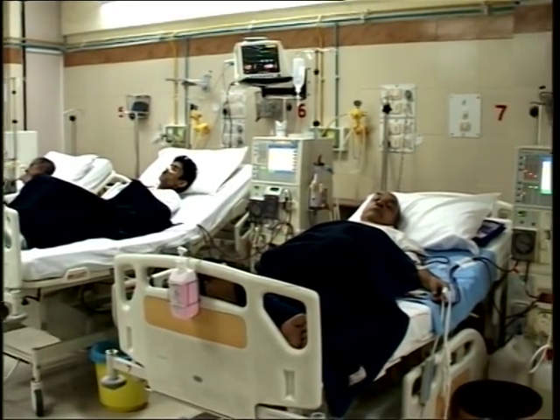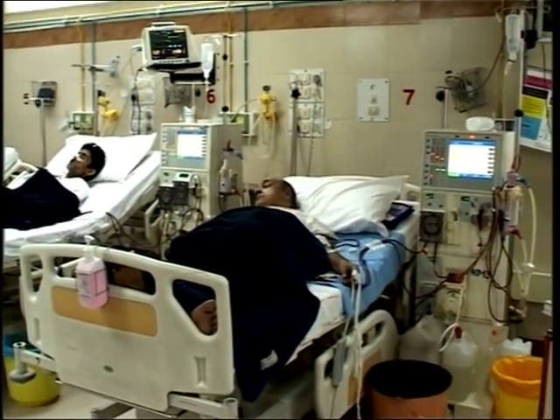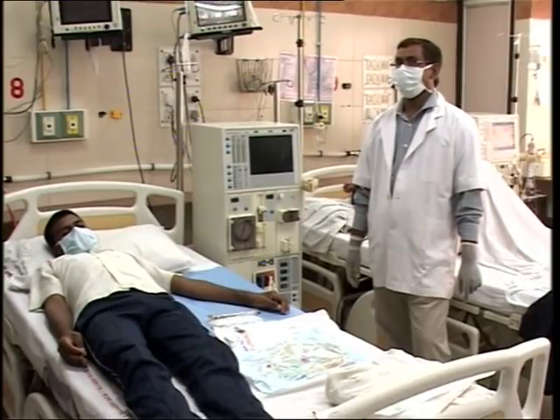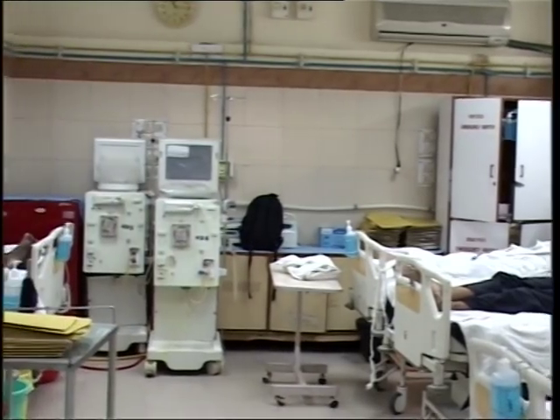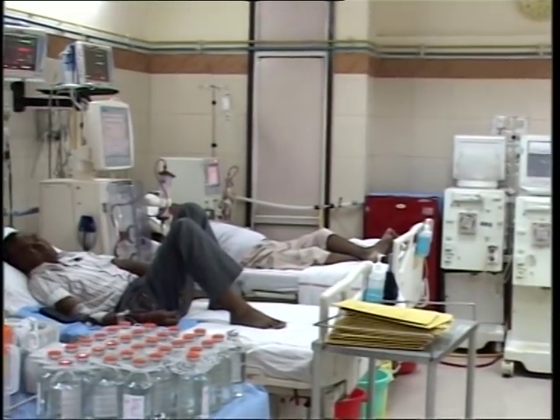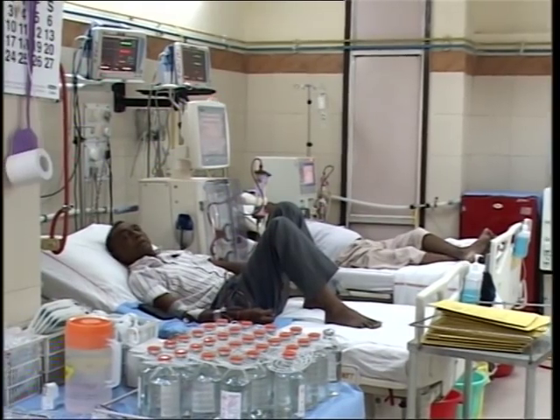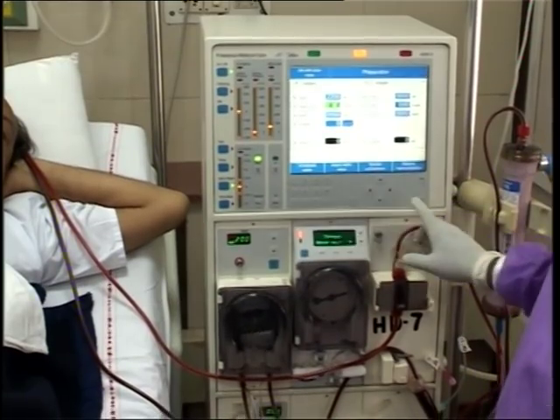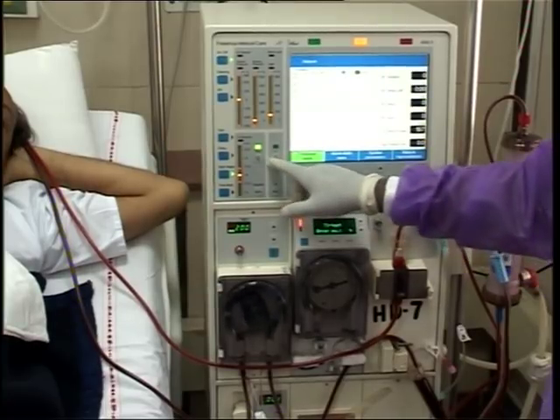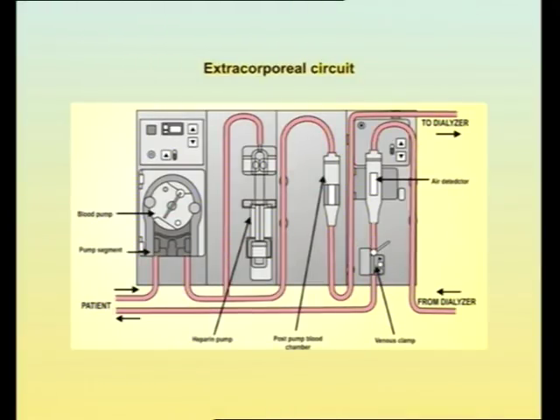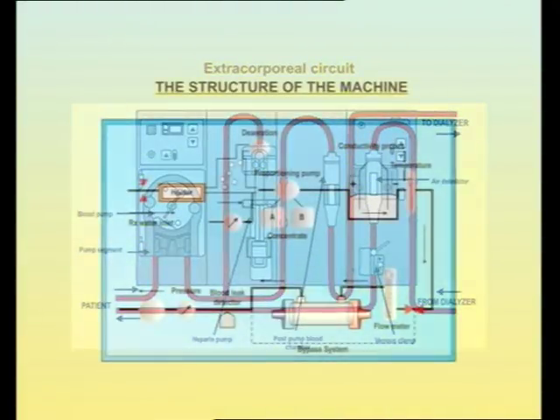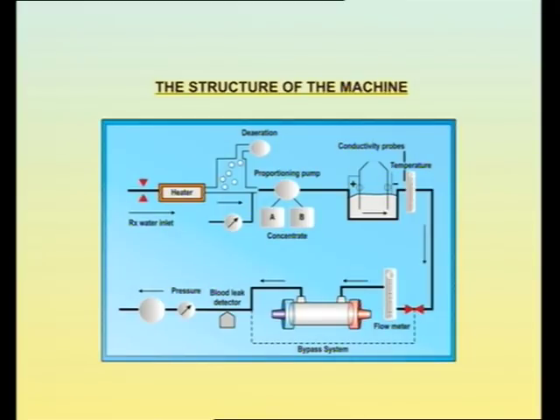Hemodialysis is the extracorporeal process which removes the accumulated uremic toxins, corrects the electrolyte imbalances, and removes fluid from the body. The blood and dialysate are separated from each other by a semi-permeable membrane, permitting solute and water transfer through the process of diffusion and convection. The integrated system of the hemodialysis machine allows the operator to control the blood and dialysate circuits and monitor important variables associated with hemodialysis.